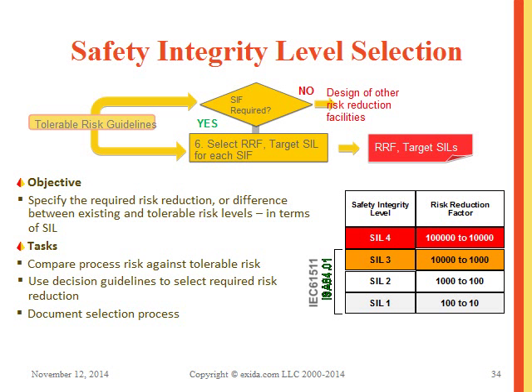The objective of the safety requirement specification is to specify the required risk reduction — the difference between existing and tolerable risk levels in terms of SIL. The tasks are to compare process risk against tolerable risk, use decision guidelines to select the required risk reduction, and document the selection process. For all safety instrumented functions defined, specific information must be documented: specific conditions sensed, actions to be taken, timing, maintenance and bypass requirements, and any special requirements needed to properly reduce the risk.